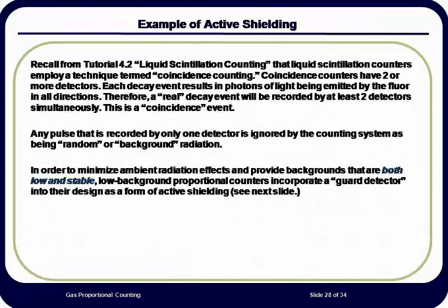Liquid scintillation counters used a technique to reduce background called coincidence counting. Due to the fact that all radiation events from the sample would cause fluor molecules to emit scintilla of light in every direction, there was a high probability of these scintilla being detected simultaneously in the two detectors surrounding the liquid scintillation cell. This was termed coincidence counting since both detectors had to receive a scintilla in a short time frame for the count to be recorded.